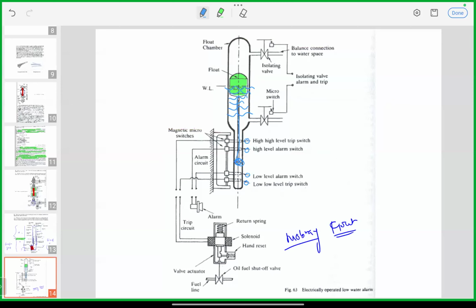And whenever it comes into magnetic contact with the magnetic switches, for example when the water level drops, it will come down, so it is going to give the low level alarm. The circuit gets completed and generates the low level alarm. With a further decrease in level, the small magnetic float moves further down and gives you the low level trip. Similarly, when the level increases, what will happen? High level alarm and high level trips are provided.